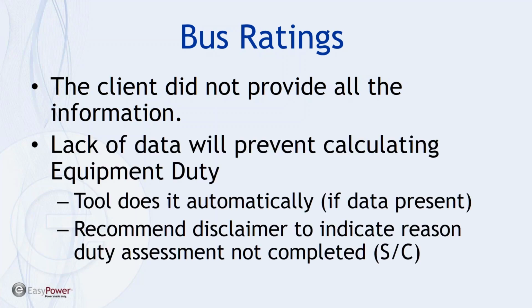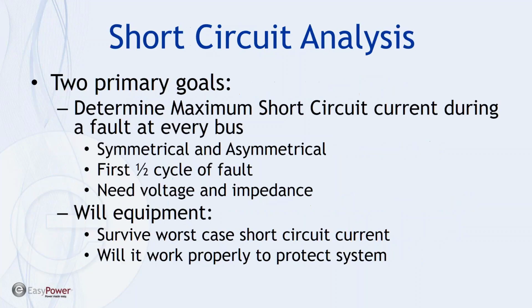The lack of the data will prevent the equipment duty function of the tool from operating properly, and in some ways it's kind of a false sense of security because you're not seeing any errors. And if you get right down to it, the primary step and the reason for the first step in an analysis is to complete the short circuit analysis, which has two primary goals. One is determining the maximum short circuit current that will be seen at any given point in the system.